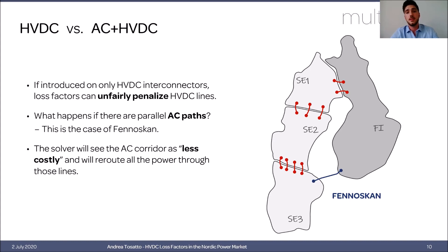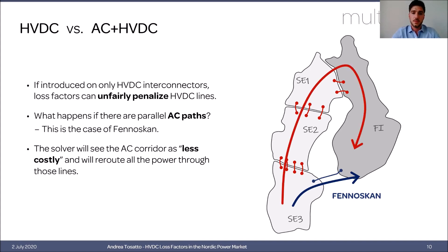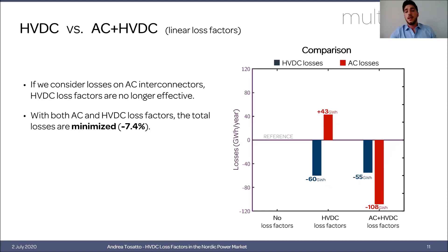The second analysis shows that AC loss factors must be included if we want to include losses in the market clearing. When there is a parallel AC path to an HVDC one — as is the case with Fennoskan, the interconnector connecting Sweden to Finland — the solver will assume that using the AC path creates no losses, which is not true. As a result, it may redirect flow over the AC path, potentially creating even more losses. The results confirm this: with only HVDC loss factors, HVDC losses decrease but AC losses increase.